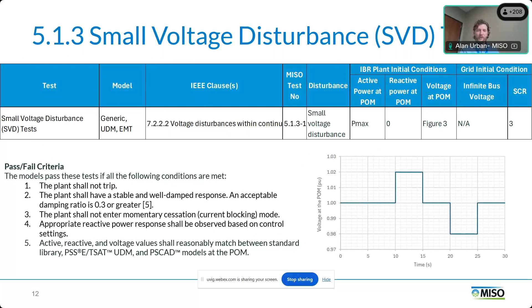Small voltage disturbance tests. On the lower right part of the slide, you can see what we're specifying for the voltage at the point of measurement. The idea here is that we're making sure the plant doesn't trip, has a stable and well damped response, is not entering momentary cessation, and that the reactive power is doing what it's expected to do based on the control settings.